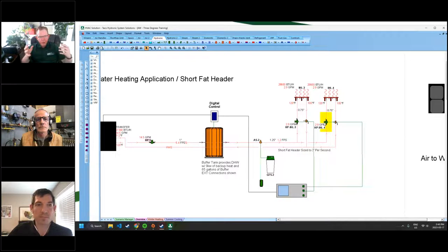And the reality is that with boilers right now, if somebody calls and complains because it's on closely spaced T's that, hey, Max, the master bedroom isn't getting enough heat, well, Max is just gonna turn the boiler temperature up. And that's going to solve it. It's not great, but it beats repiping it. You can't do that on a heat pump. There is no going in and going, I'm just going to turn the temperature up and sort of hope for the best.